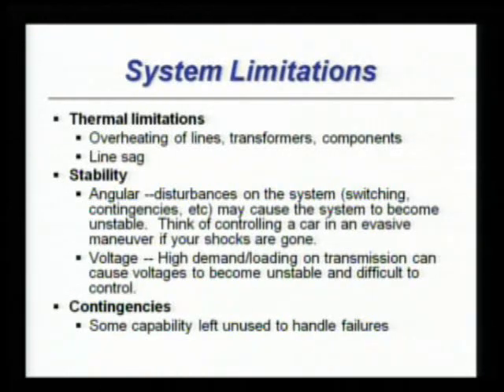Stability issues—again, think of the system like mass spring systems from basic physics. When the system gets thumped, something happens like a big load switching off, a switching event, a lightning strike, or a generator tripping off, the system has a thump to it and starts to oscillate. If the system isn't designed properly, it will oscillate and lose synchronism, and you'll lose more than you anticipated from that system thump. So you have angular stability issues, voltage stability issues—all of these are system limitations.